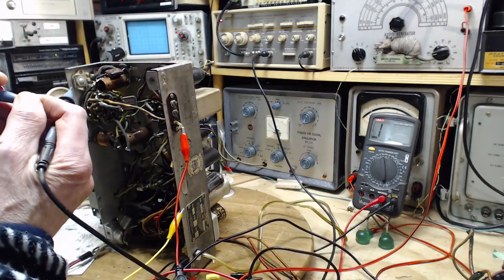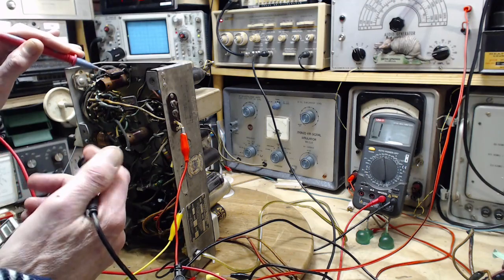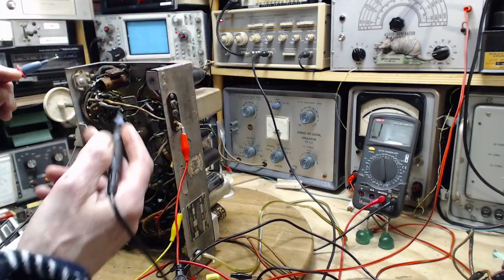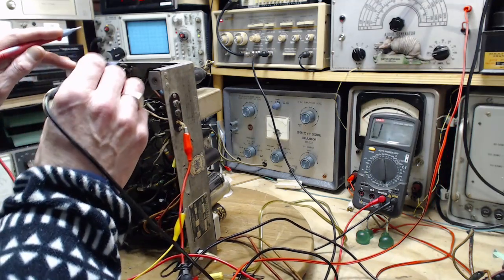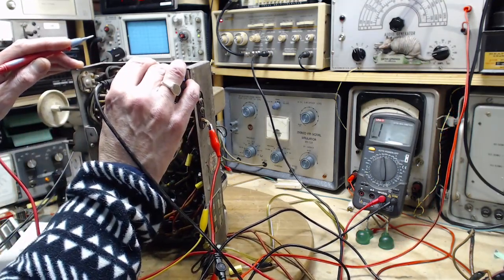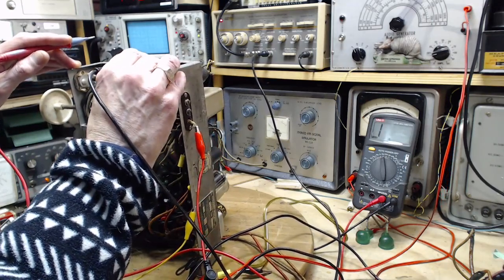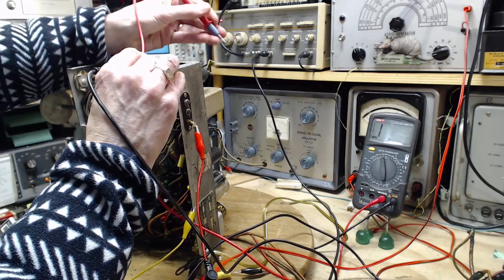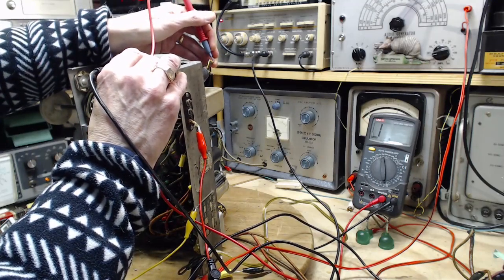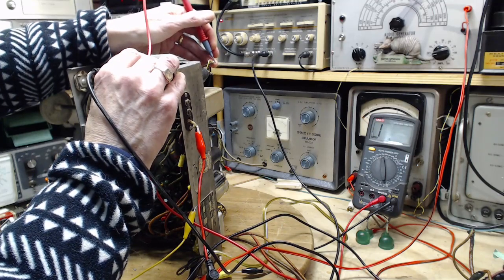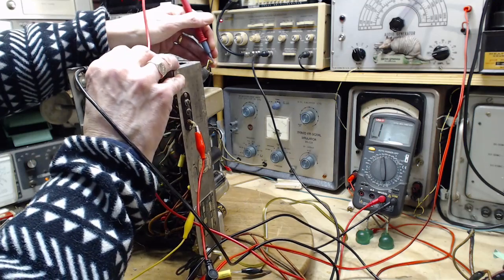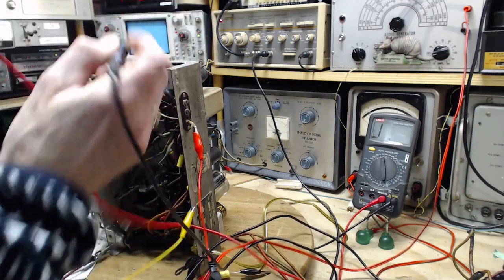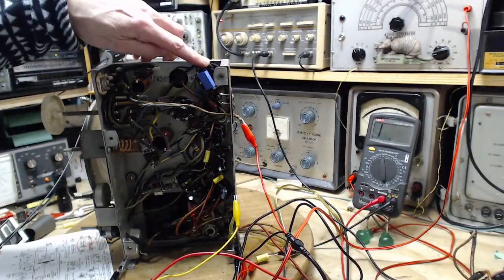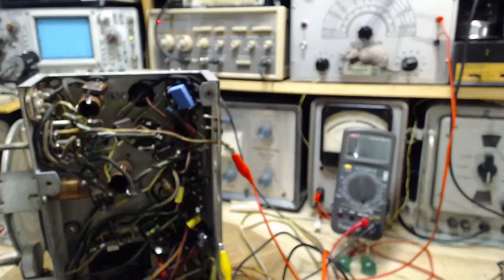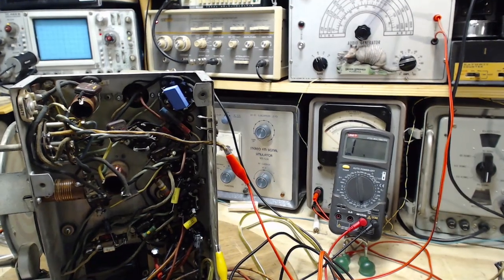So what I'm doing is I'm testing the primary and the secondary. The primary with the ohm meter looks fine. Secondary, maybe not. So getting on one leg here and the other up here, and this should look like pretty much a short circuit. And 0 happening. Maybe I'm on the wrong terminal here. Unfortunately, they have a whole pile of black wires all piled up on top of each other here. And in order to see what's happening, I have to use my X-ray vision.